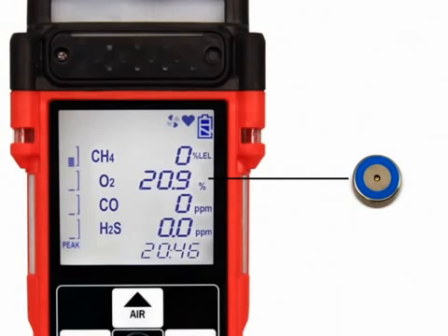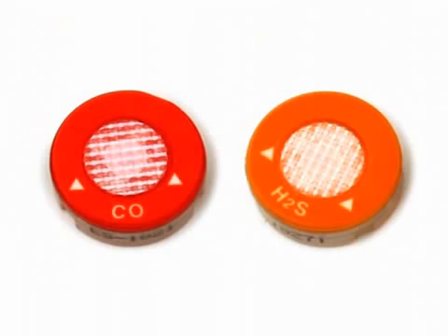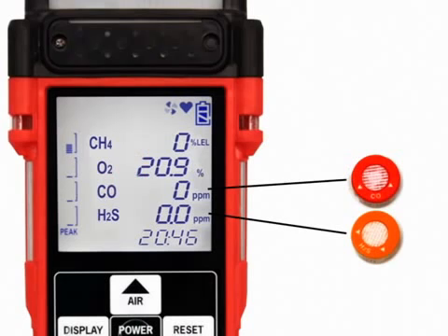LCD display. The CO and H2S sensors are electrochemical sensors that consist of 2 precious metal electrodes in an acid electrolyte. A gas-permeable membrane covers the sensor face and allows gas to diffuse into the electrolyte. The gas reacts in the sensor and produces a current proportional to the concentration of the target gas.